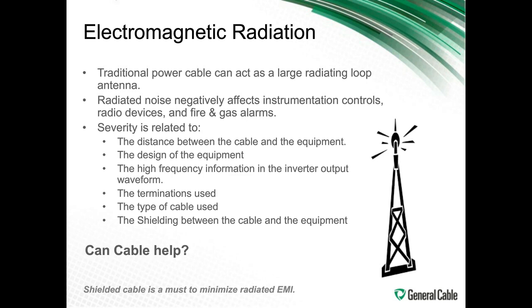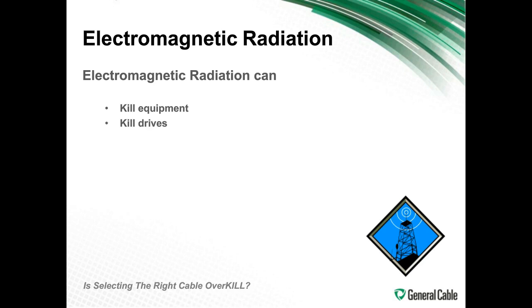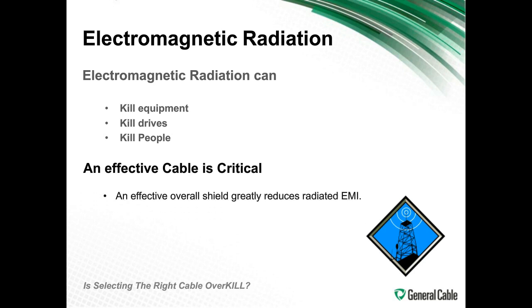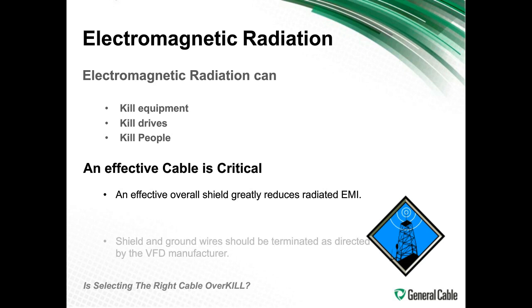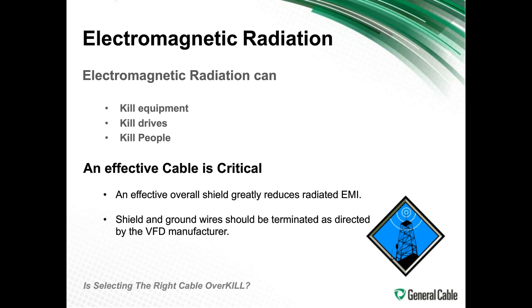So is the cable important here? Electromagnetic radiation is very important to account for. Why? Because it can kill equipment, it can kill drives, and it can kill people. This is very important. So an effective cable is critical. An effective cable can have an overall shield that greatly reduces that radiated EMI. The shield and ground wires need to be terminated as directed by the manufacturer of the drive, and there needs to be a 360-degree termination of the cable shield to make sure you have a good, effective cable system.